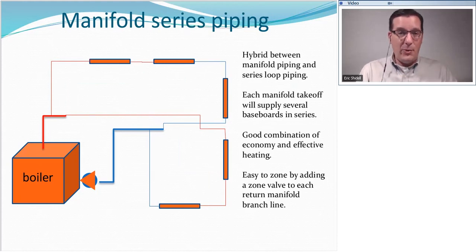A kind of halfway compromise between the two is called the manifold series piping. And here the distribution network is broken up into zones where we'll have several emitters in series, but not all of them. So this really simplifies the installation. We get the best of all worlds in that each emitter is pretty much getting the warm water that it needs. And we eliminate that kind of, you know, redheaded stepchild zone that isn't getting heated properly. And we get pretty decent economy, really good heating, and it's kind of the best of all worlds.